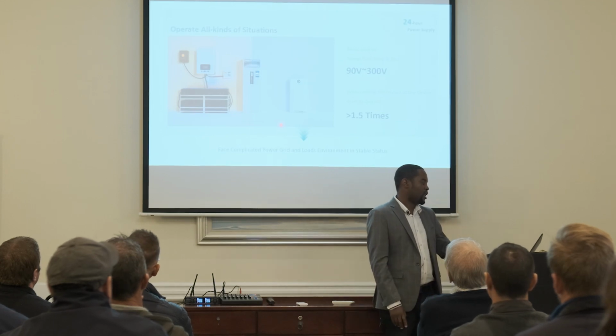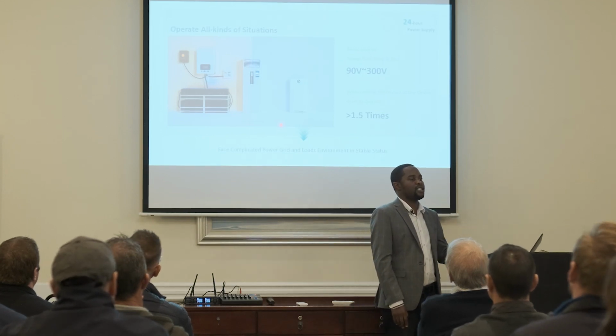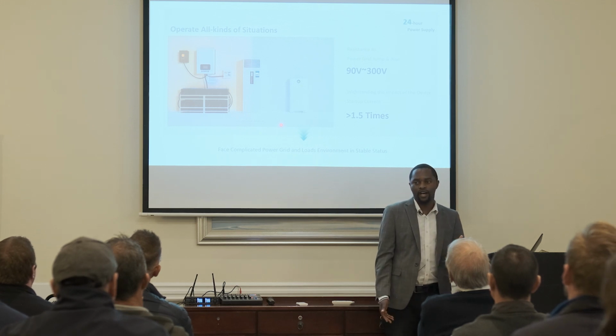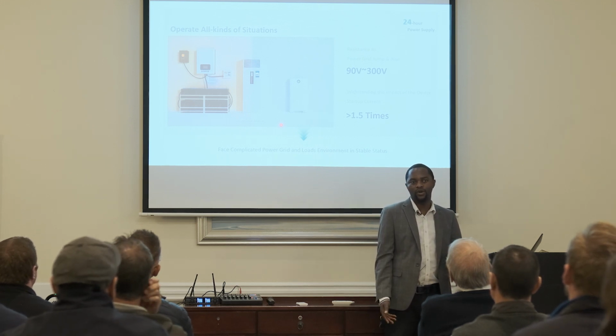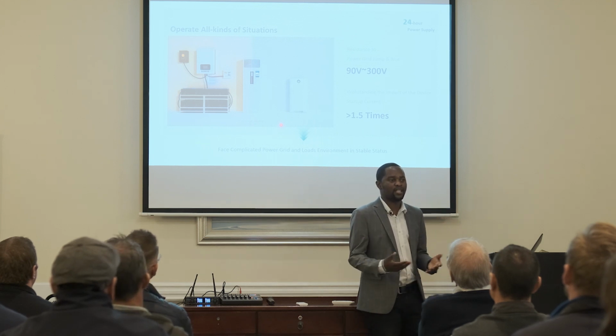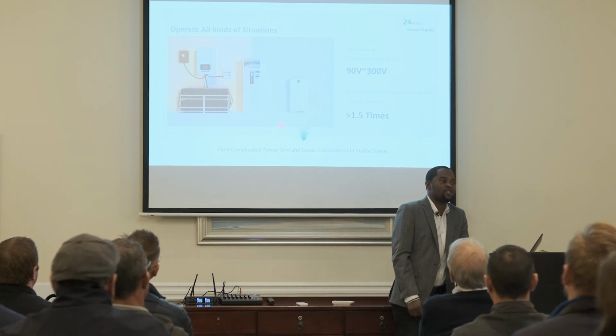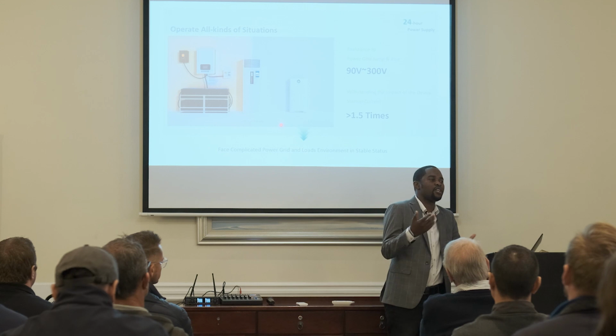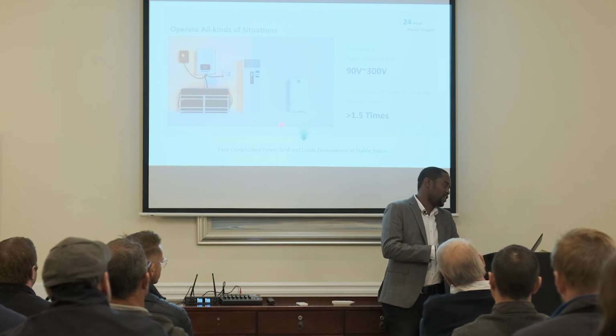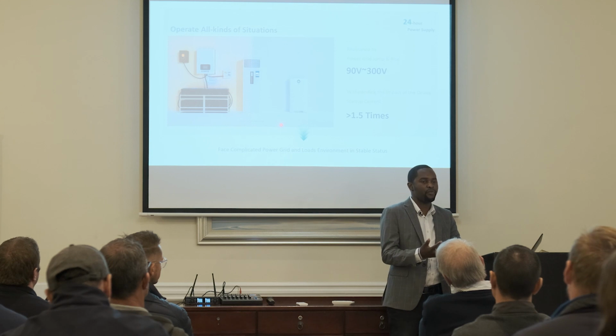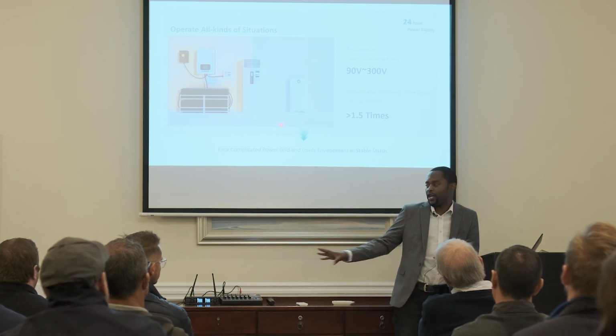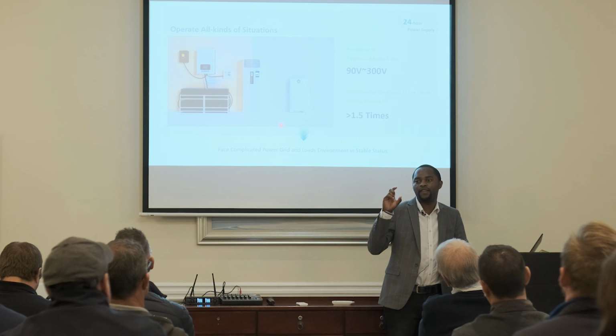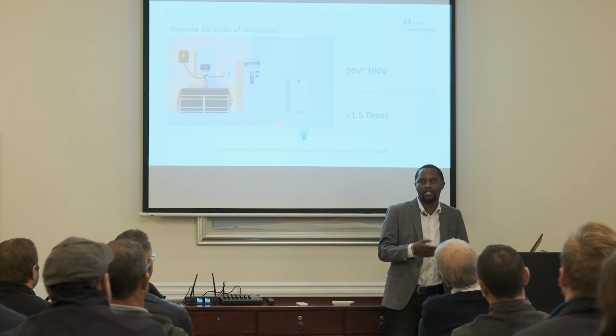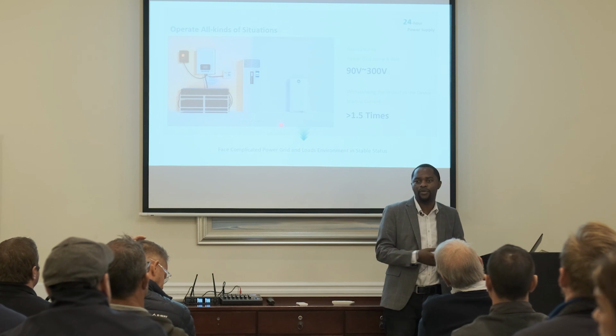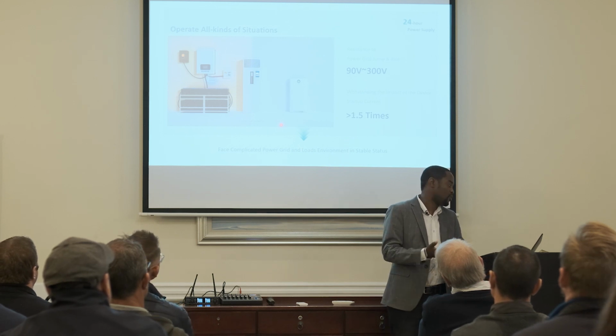Then this is just showing you that for startup currents, it can withstand up to 1.5. This is also important when you've got inductive loads on site. As you know, an inductive load can take more than its size, maybe up to 5 or 10 times. So there's no guarantee. If it's a 2 kilowatt inductive load, when it's starting up, it can actually draw 4 kilowatt or 6 kilowatt for a few seconds. The inverter also helps you to cater for that, up to 1.5 its size, which means a 5 kilowatt inverter can actually give you 7.5 kilowatt for a few seconds to allow starting of maybe your air cons, a pump on site, or multiple fridges, all those inductive loads.